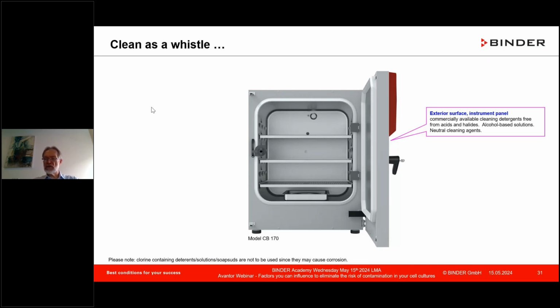Here you can use commercially available detergents, but all of them must be free of acids and halides, because if they contain acids and halides, corrosion risk will increase, and that is not only an aesthetic thing, but also has to do with reliability and contamination prevention. Alcohol, naturally 70%, is okay, or neutral cleaning agents.